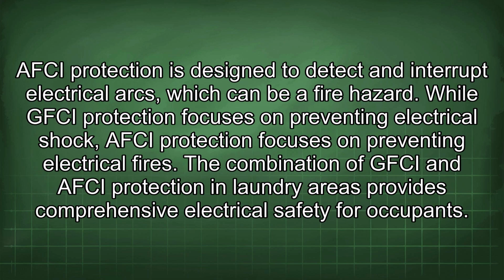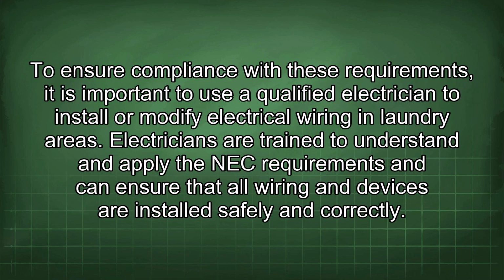AFCI protection is designed to detect and interrupt electrical arcs, which can be a fire hazard. While GFCI protection focuses on preventing electrical shock, AFCI protection focuses on preventing electrical fires. The combination of GFCI and AFCI protection in laundry areas provides comprehensive electrical safety for occupants. To ensure compliance with these requirements, it is important to use a qualified electrician to install or modify electrical wiring in laundry areas. Electricians are trained to understand and apply the NEC requirements and can ensure that all wiring and devices are installed safely and correctly.